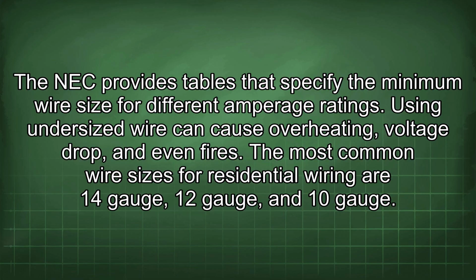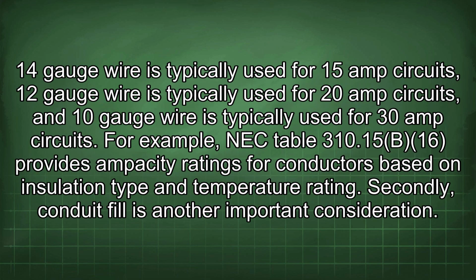The most common wire sizes for residential wiring are 14 gauge, 12 gauge, and 10 gauge. 14 gauge wire is typically used for 15 amp circuits, 12 gauge wire is typically used for 20 amp circuits, and 10 gauge wire is typically used for 30 amp circuits. For example, NEC Table 310.15(B)(16) provides ampacity ratings for conductors based on insulation type and temperature rating.